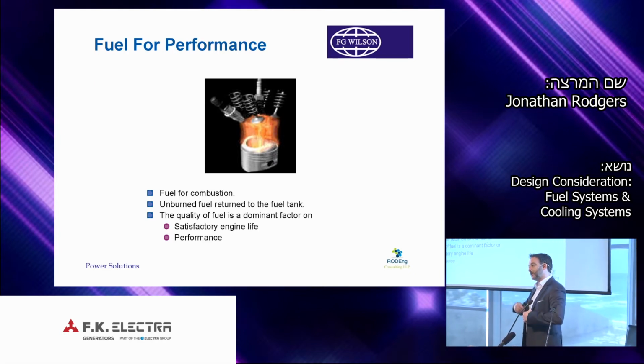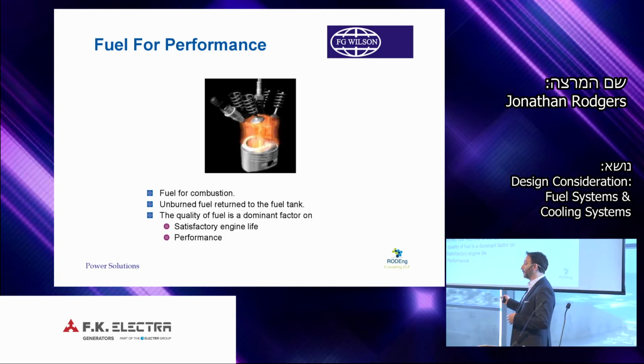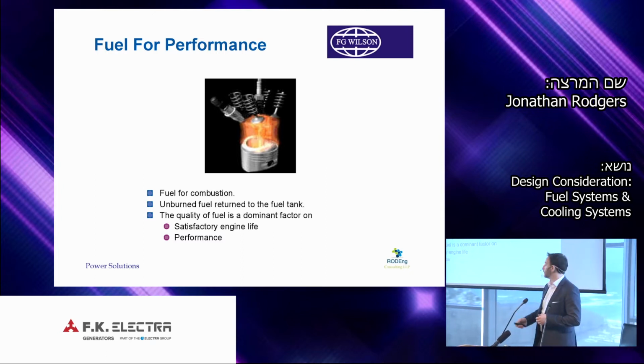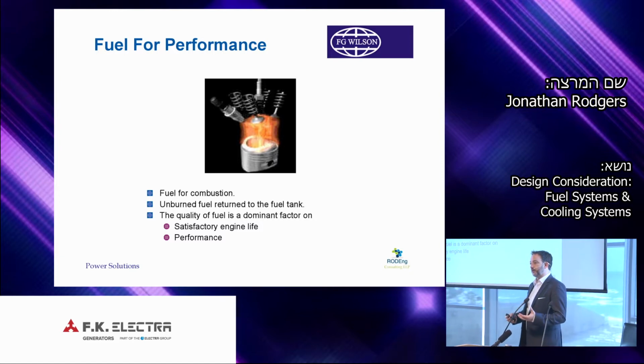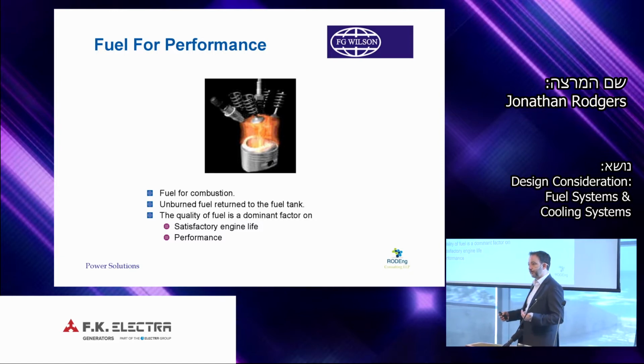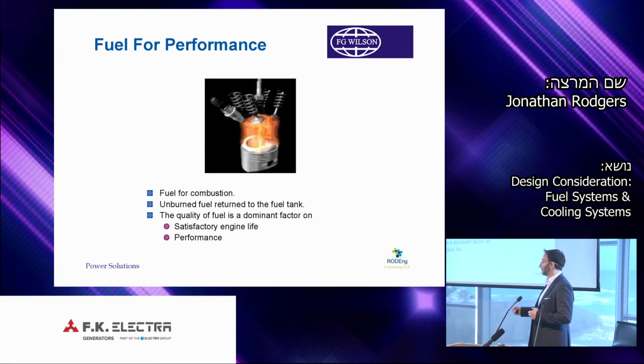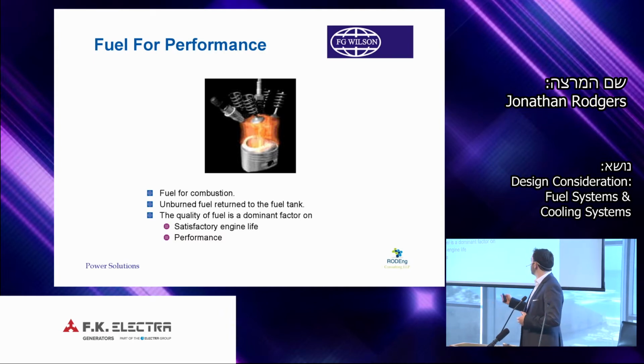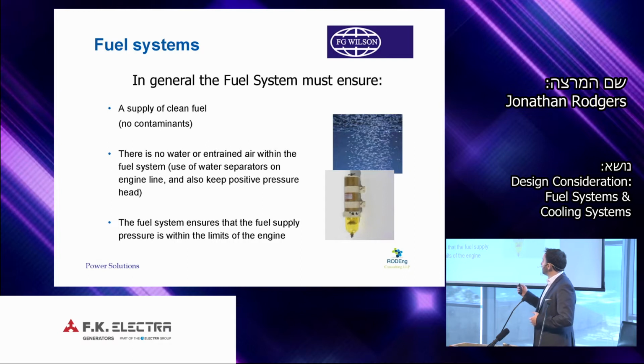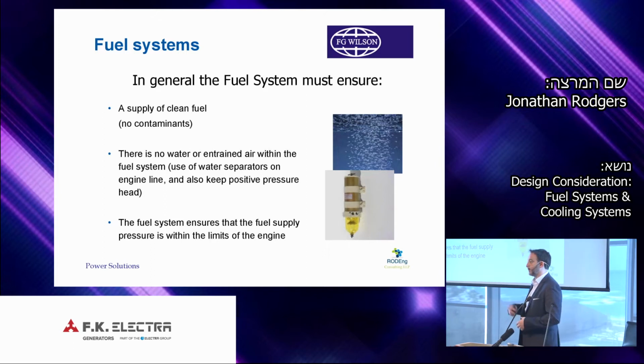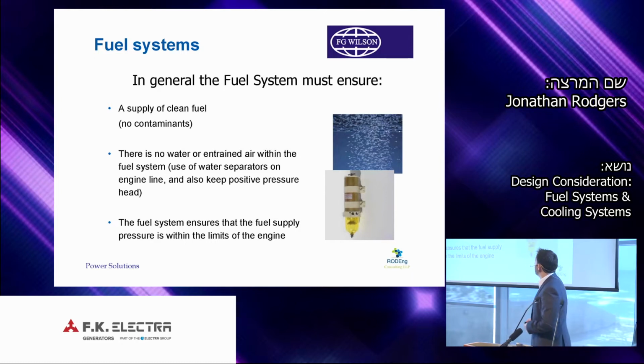We also have fuel that's supplied to the engine and returned back to the fuel tank, and that's the unburnt fuel that cycles around the fuel system. And then the quality of the fuel, the type of fuel and quality of the fuel, this directly reflects on the life of the engine and obviously the performance, how much energy we can have from the generator set. So in the supply of fuel, it's not just fuel quality, it's also what is within the fuel. So contaminants, dust, sand, also water.